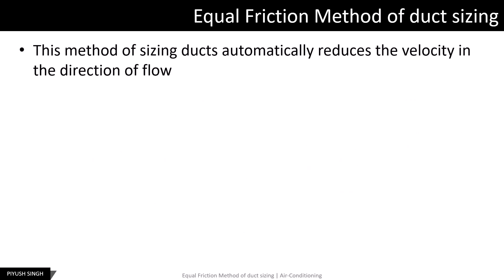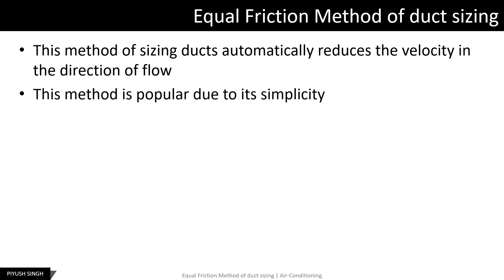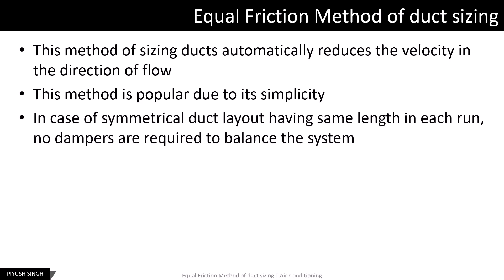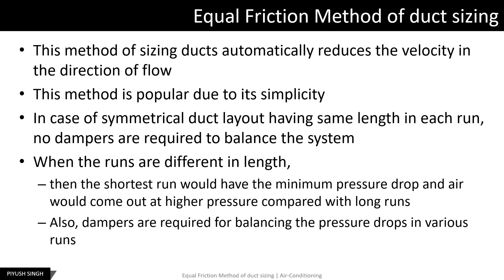In this method of duct sizing, the velocity reduces in the direction of the flow. This method is very popular due to its simplicity. In case of a symmetrical duct layout having the same length in each run, no dampers are required to balance the system. However, when we have asymmetrical duct systems, the shortest run would have the minimum pressure drop and air would come out at higher pressure compared with longer runs.